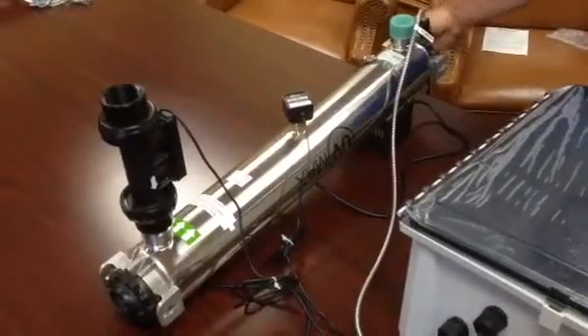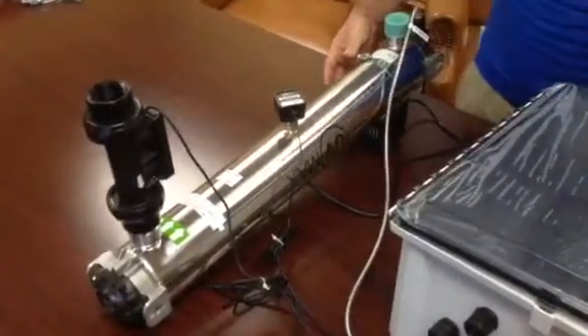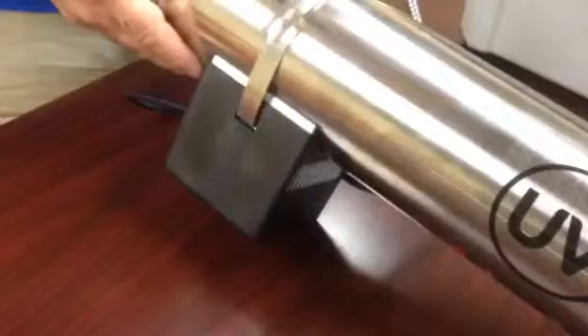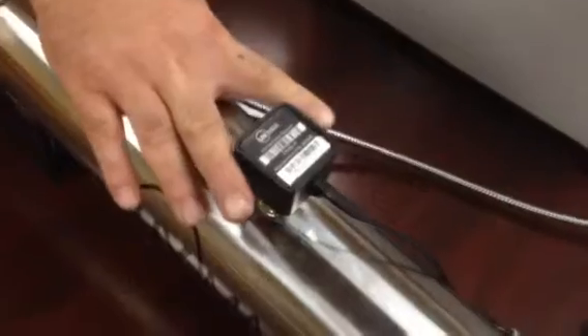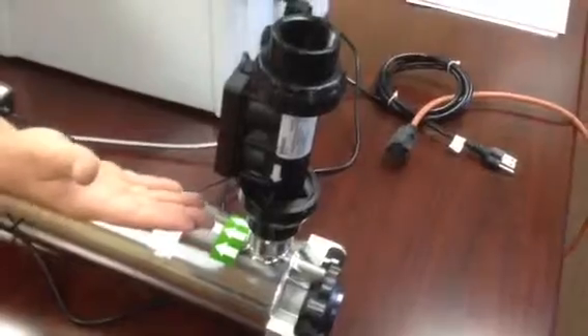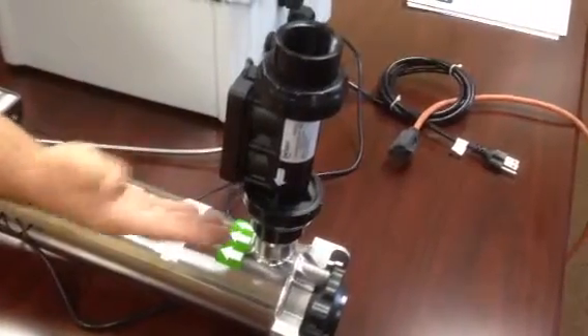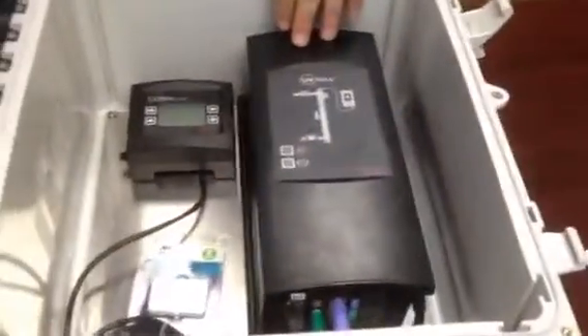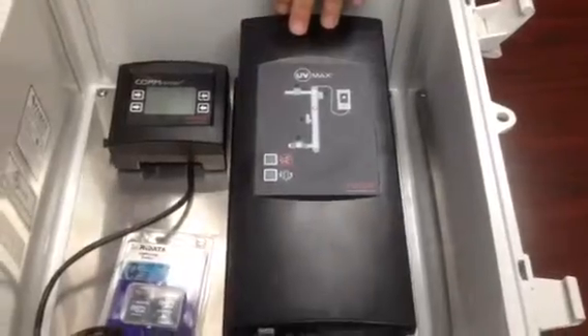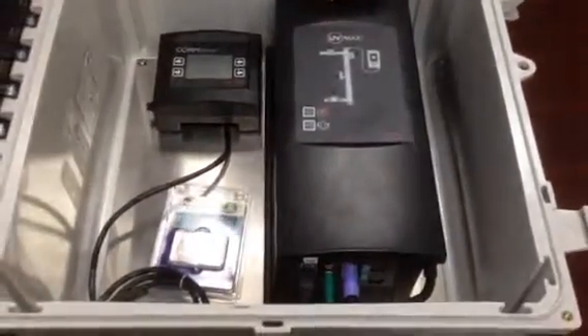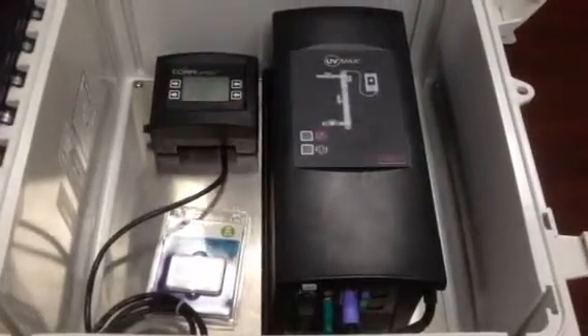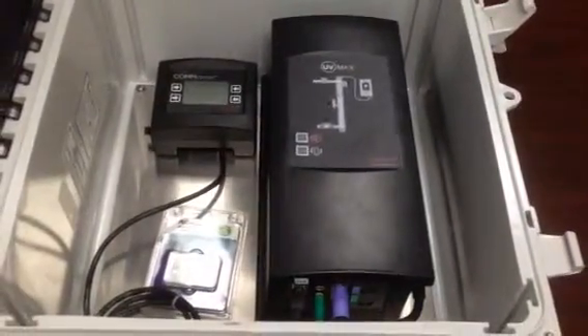The minor parts of the system that come with every UVMax Pro are the cooling fan, which is on the bottom of the unit and keeps it cool when no water is flowing through it; the UV intensity sensor, which measures the strength of the UV; and the flow sensor, which measures the water flow into the unit in real time. Because it measures the flow of the water in real time, the power supply is able to calculate the real-time dosing—how much UV is actually going into the water based on the flow, not based on a static max flow amount that it assumes is always the case.